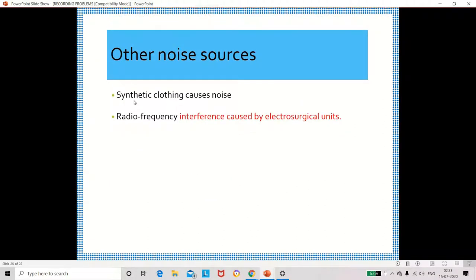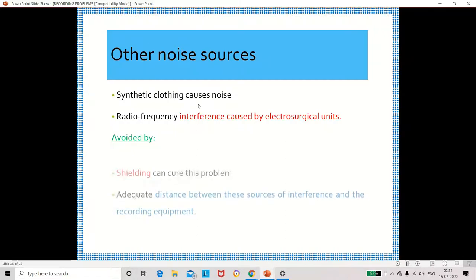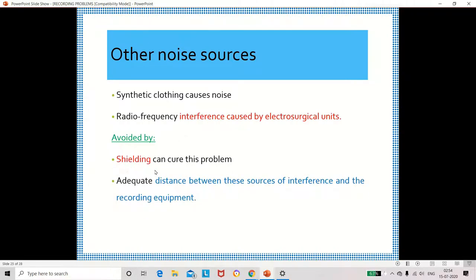Other noise sources include the use of synthetic clothing, which may create noise, and the use of electrosurgical units, which may create interference. These can be avoided by choosing proper clothing, using shielding while measuring biosignals, and keeping the recording equipment at a distance from the source of interference.